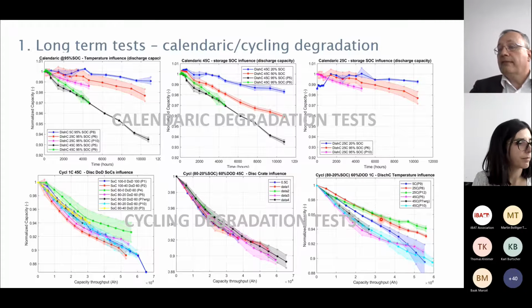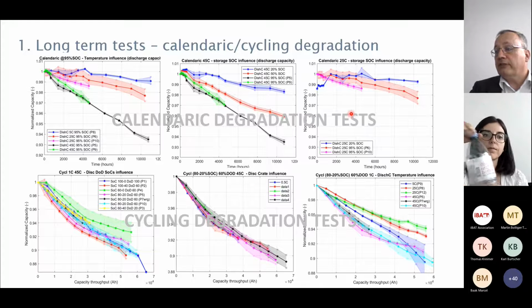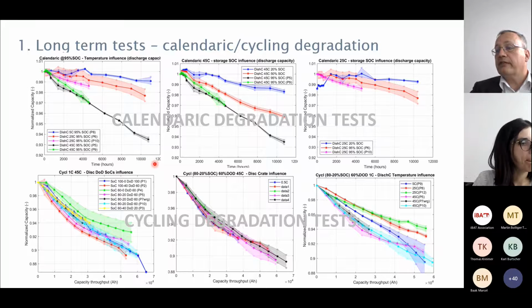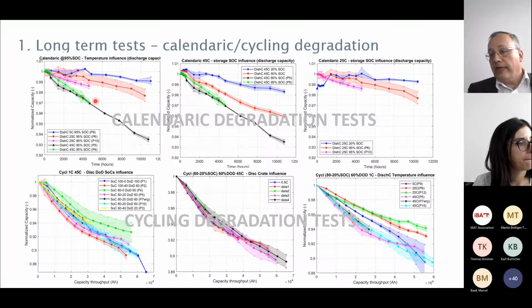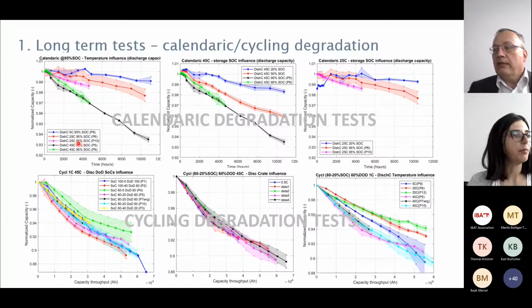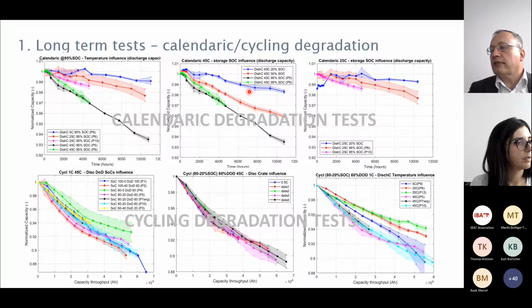We do long-term tests. As you can see here, on top is the calendaric degradation test. The number of hours here - this is a test which was run over a year. And from time to time, as we said, we did these reference cycles. These are the same battery, but for different types of state of charge for storing, and there you can see the impact - in this case here it's the temperature impact, and here is the average state of charge impact. As you can see, if it's fully charged, it's decreasing much faster than if you have an average SOC of 20% in this case - this is 45 and this is 20 - and that's for different temperatures.